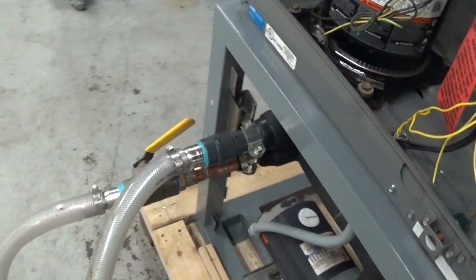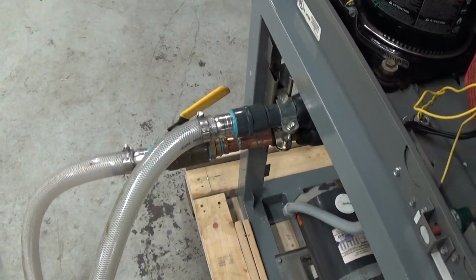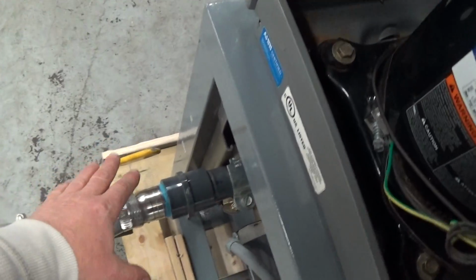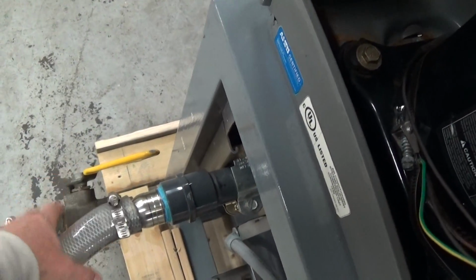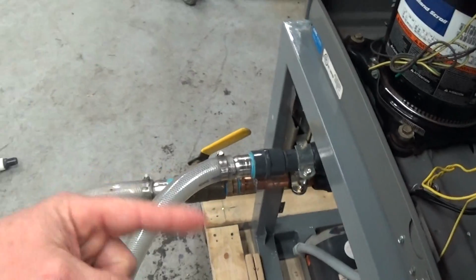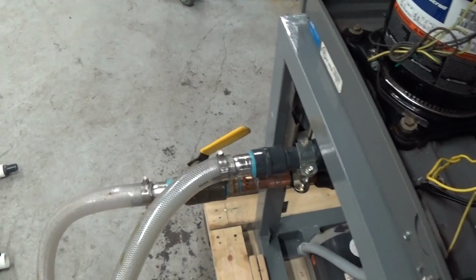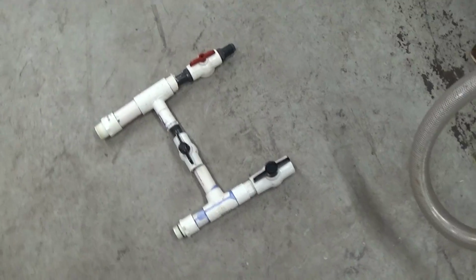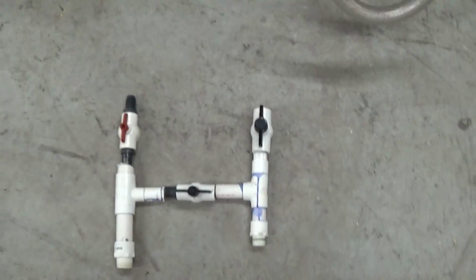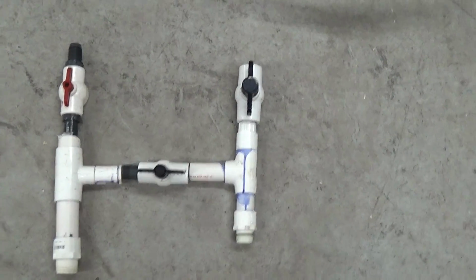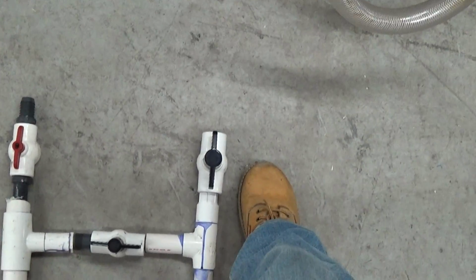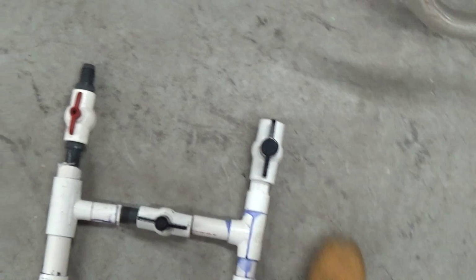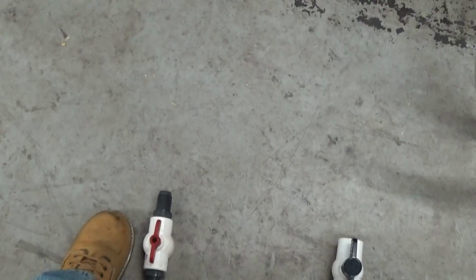This chiller here, when you do get it, you want to put a shut-off on both the inlet and outlet. You also want to hook up a tiny little bypass with a third shut-off. I just set up this little mock display on the floor here. I grabbed some PVC stuff out of the bin so you can understand what I'm talking about. So you're going to put a shut-off on the outlet and a shut-off on the inlet.